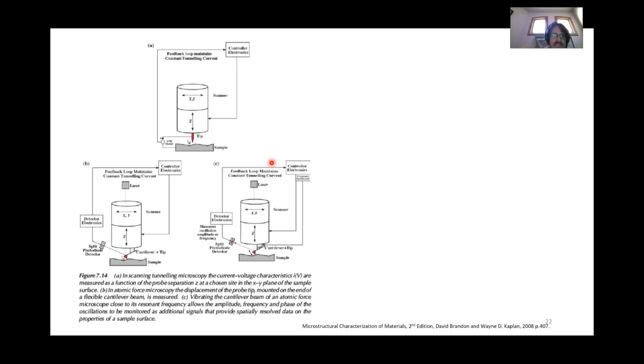Kind of some schematics talking about the different microscopes. So this is an STM microscope, and these are atomic forces. So the difference between an STM microscope, you're dealing with the tunneling current. The probe is riding just above the surface. On an AFM, the tip is actually on a cantilever. Okay, so it is a little bit different because you can actually move the cantilever. And so there's some other things you can do. So you can do contact and also contactless type of probing.